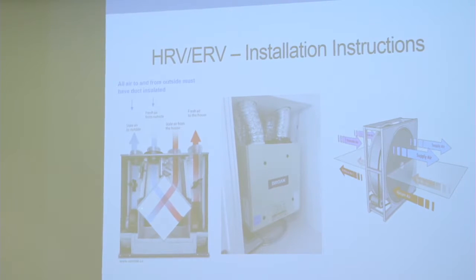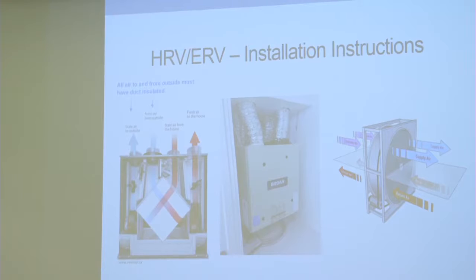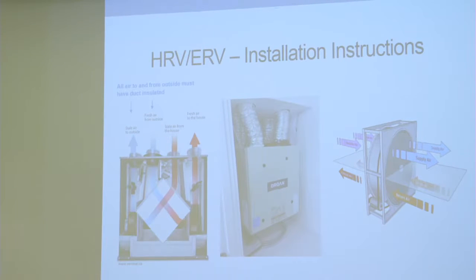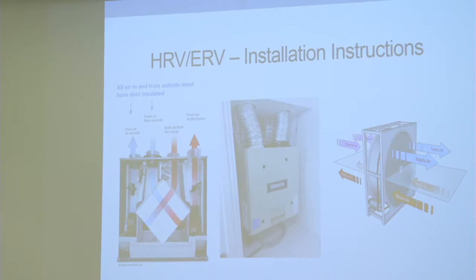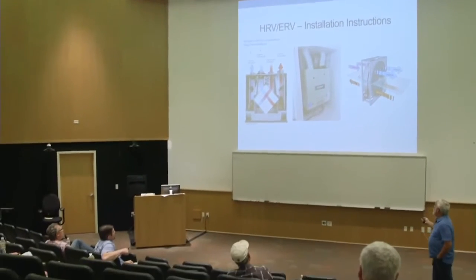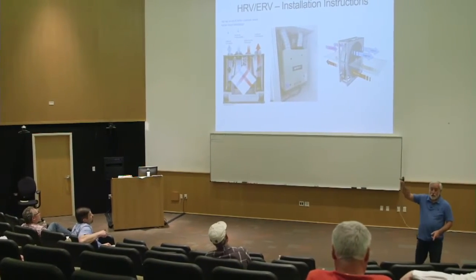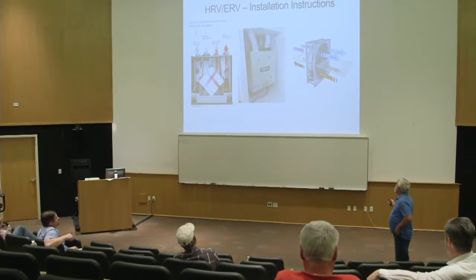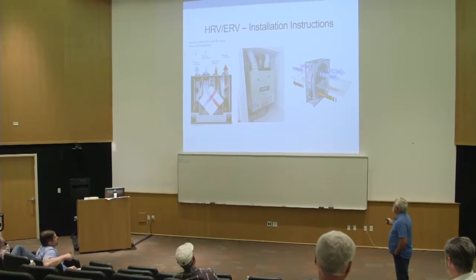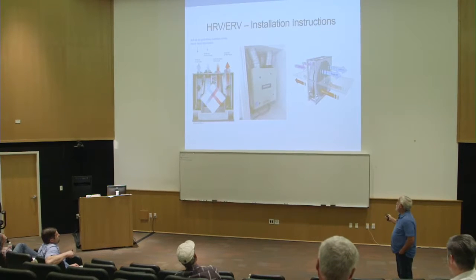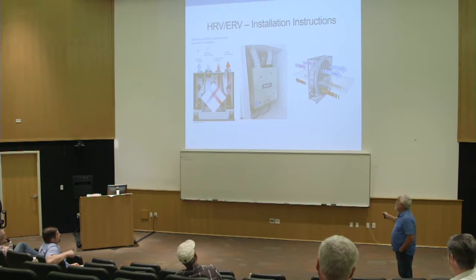But this ERV, this is a desiccant material, so if you're in Biloxi, Mississippi, and you're bringing in that moist air, the heat exchanger absorbs the moisture and then it's transported back outside. Or if you're here, the moisture that we're exhausting out is absorbed by the heat exchanger and we bring it back into the house. This is a wheel type design where there's actually this wheel that's turning, and it's a desiccant material. So we have fresh air coming in, exhaust air going out. It absorbs the moisture, absorbed into that desiccant wheel, and then taken back outside. That's the difference.